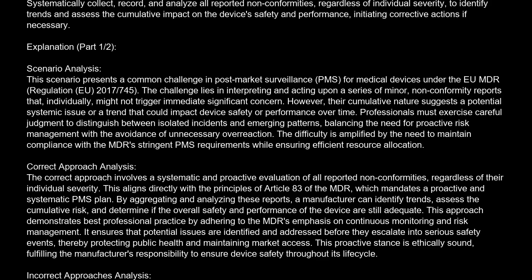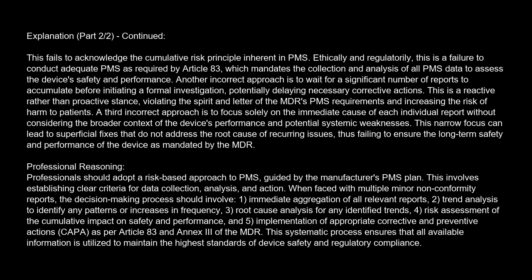One incorrect approach is to dismiss the reports individually because they are minor and do not meet the threshold for immediate serious incident reporting under Article 87. This fails to acknowledge the cumulative risk principle inherent in PMS. Ethically and regulatorily, this is a failure to conduct adequate PMS as required by Article 83, which mandates the collection and analysis of all PMS data to assess the device's safety and performance.